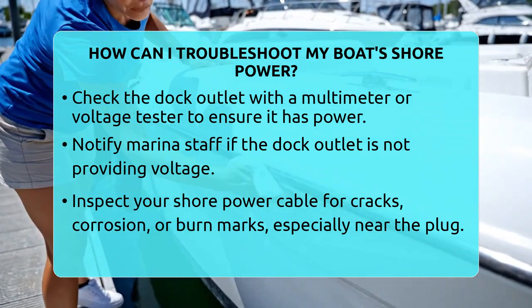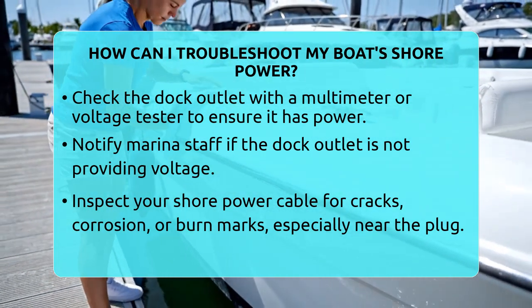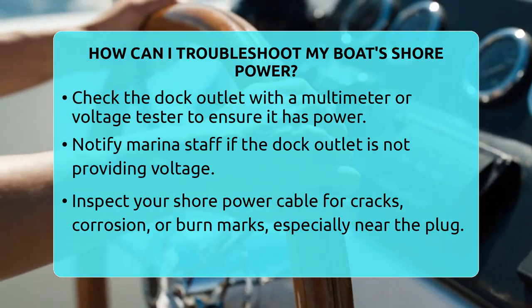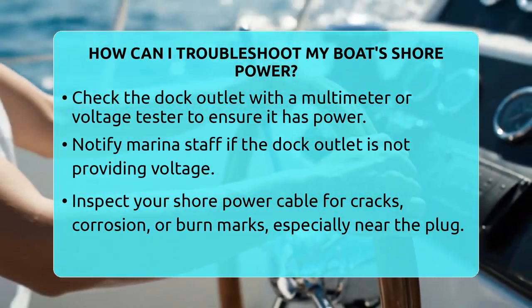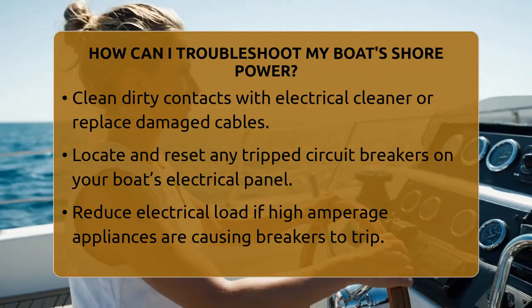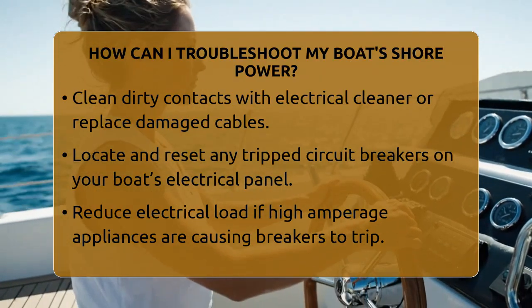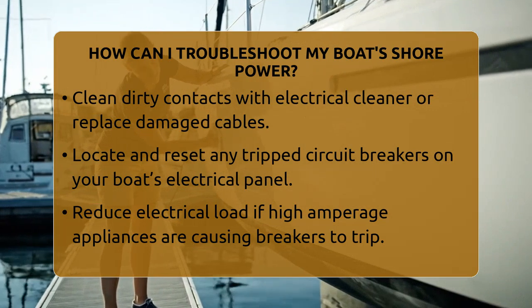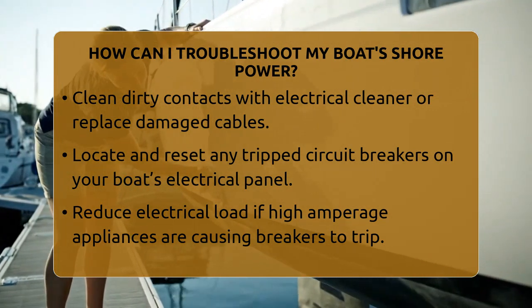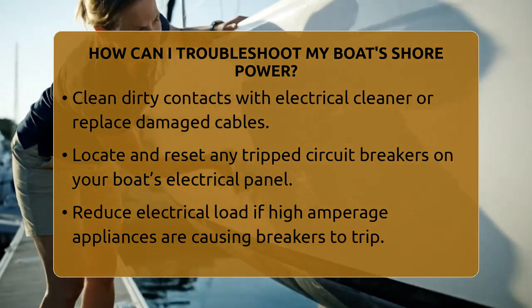Next, examine your shore power cable. Look for cracks, corrosion, or burn marks, especially near the plug ends. Salt water and vibrations can cause corrosion or loose connections, which might lead to power loss or sparks. Clean any dirty contacts with electrical cleaner or replace the cable if it's damaged.